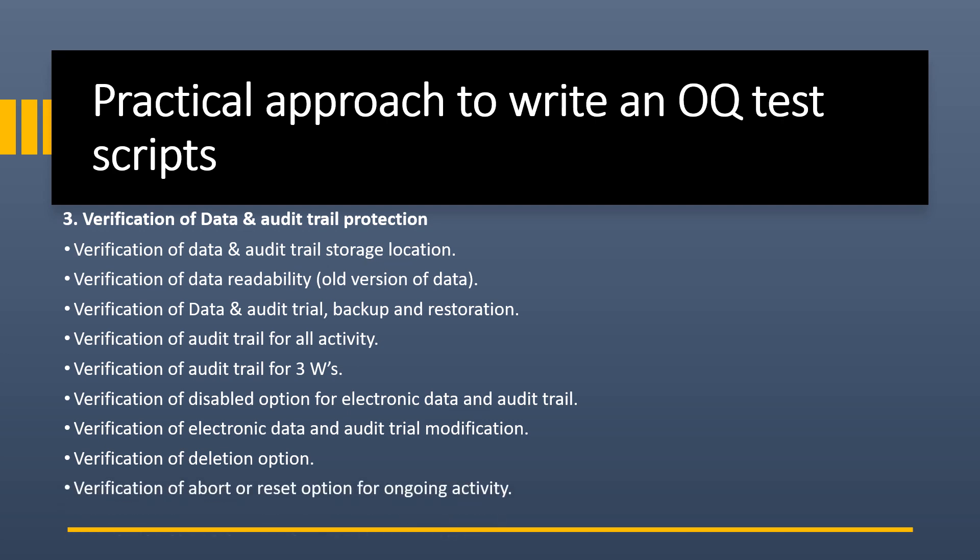Next is verification of abort or reset option for ongoing activity — if a system is running, there should be no option to stop or reset the ongoing activity; if such an event occurs, data and audit trail should still capture all activity. Next is verification of network failure protection mode, applicable for server-based systems — if the network connection is lost, data shall be stored locally and transferred to the server once the network resumes.